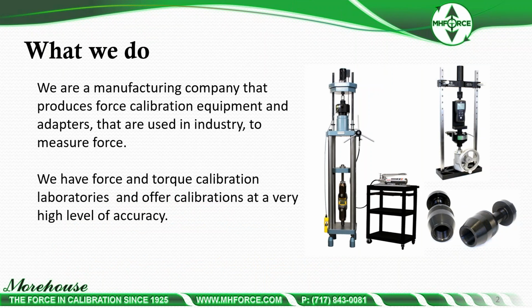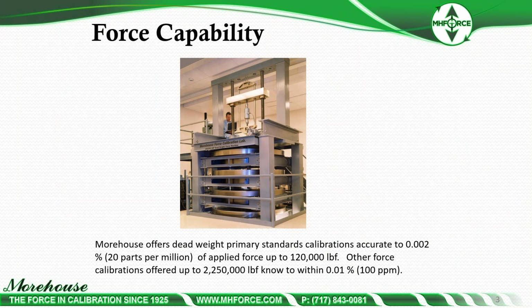What we do, we are a manufacturing company that produces force calibration equipment and adapters that are used in industry to measure force. We have force and torque calibration laboratories and offer calibrations at a very high level of accuracy. We have force capabilities up to 120,000 pounds at about 20 parts per million, and other force calibrations are offered up to 10 meganewtons, or 2.25 million pounds, known to within about 100 parts per million.